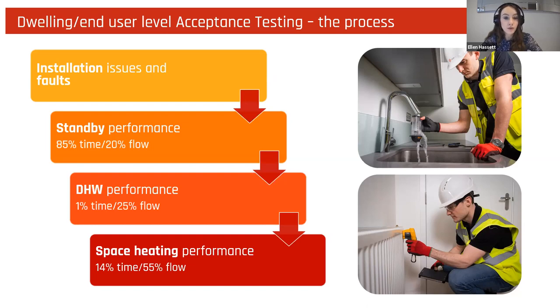And we'll look at standby performance, which involves checking heat meter data to see real-time performance. Hot water performance, which includes checking how long residents need to wait for hot water. Space heating performance, such as checking the commissioning of the heating circuits, whether they're radiators or underfloor heating, and ensuring that the heat output required for the room can be achieved. So the correct commissioning of each mode of operation is essential to network performance, as each mode either takes up a large proportion of the total flow or time in any given year, as is shown with the percentages.